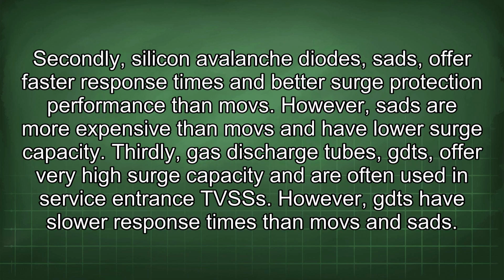Secondly, silicon avalanche diodes, SADs, offer faster response times and better surge protection performance than MOVs. However, SADs are more expensive than MOVs and have lower surge capacity. Thirdly, gas discharge tubes, GDTs, offer very high surge capacity and are often used in service entrance TVSSs. However, GDTs have slower response times than MOVs and SADs.